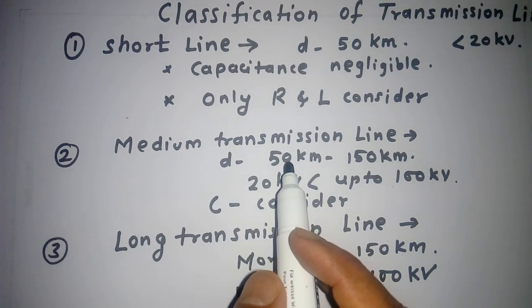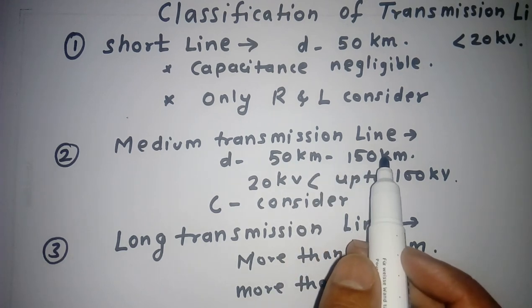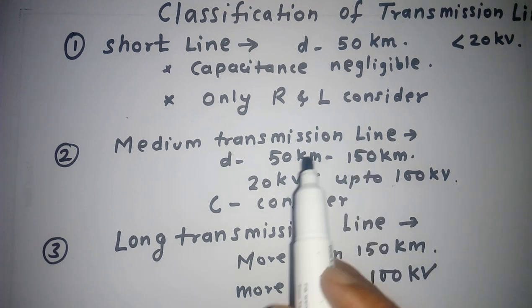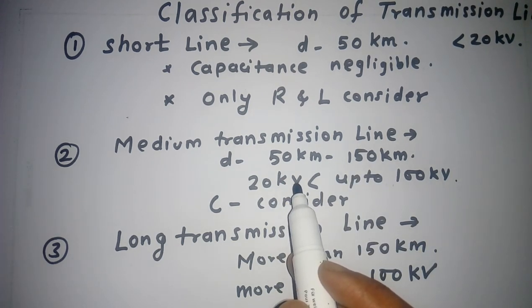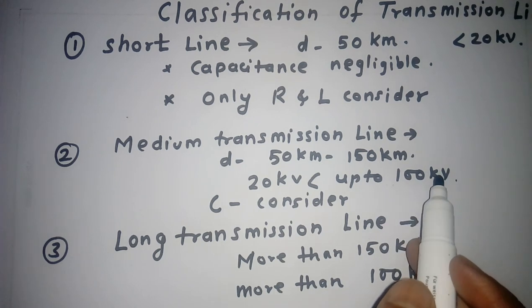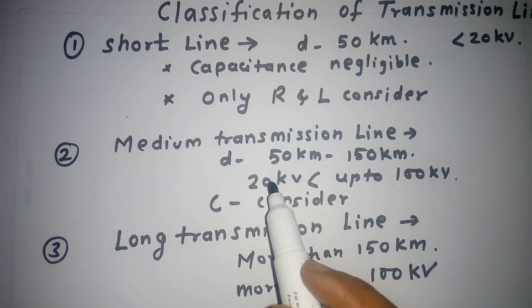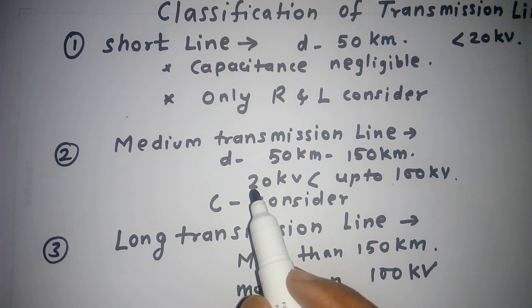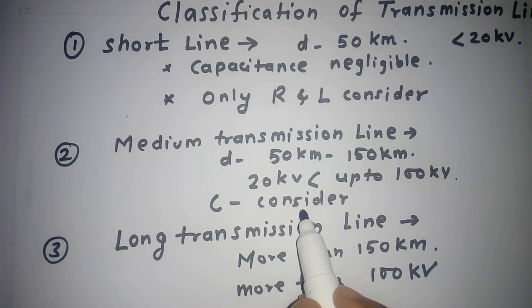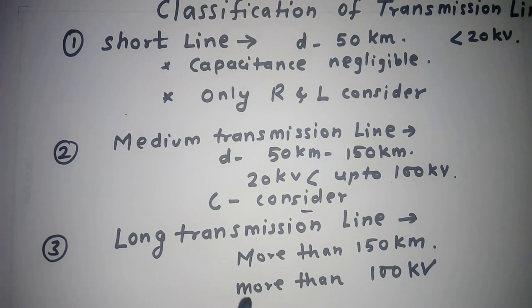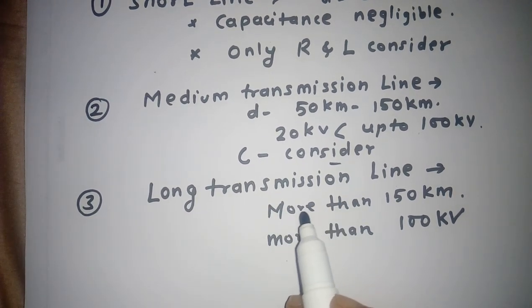The next category is the medium transmission line. Any line in the range of 50 kilometers to 150 kilometers is called a medium transmission line. The voltage level will be more than 20 kilovolts and up to 100 kilovolts. As the length increases, the capacitance effect is always considered.